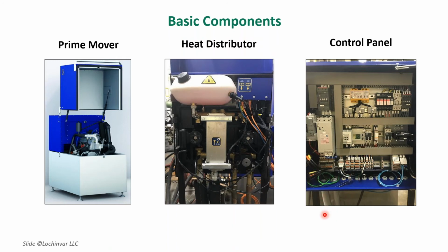What happens is we'll take that 480, come in from the line beyond the breaker box in the building, hook it up into the contactors here, then run it back to the power unit, the prime mover, the engine. We'll use that 480 to spin the generator, which at this point is a motor, so we're spinning the motor to actually start the engine as a starter.